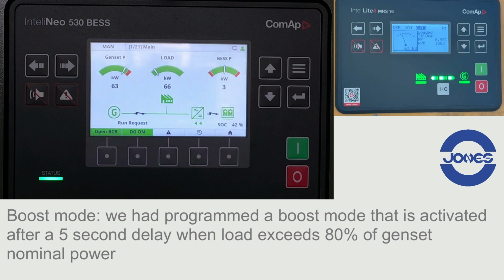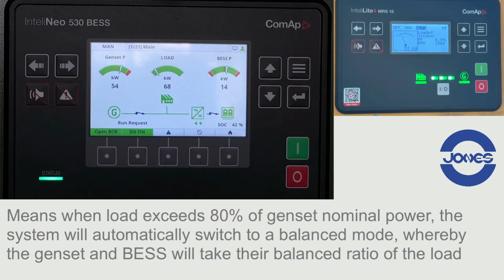Boost mode. We had programmed a boost mode that is activated after a 5-second delay when load exceeds 80% of the genset nominal power. This means when load exceeds 80% of the genset nominal power, the system will automatically switch to a balanced mode, whereby the genset and BESS will take the balanced ratio of the load.